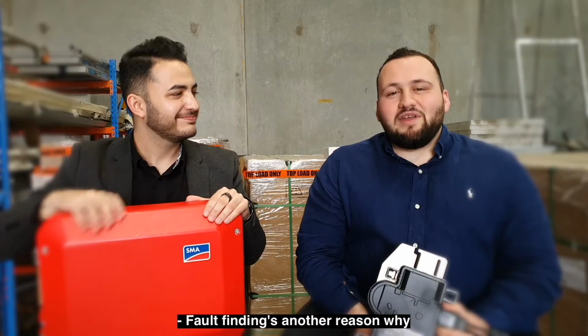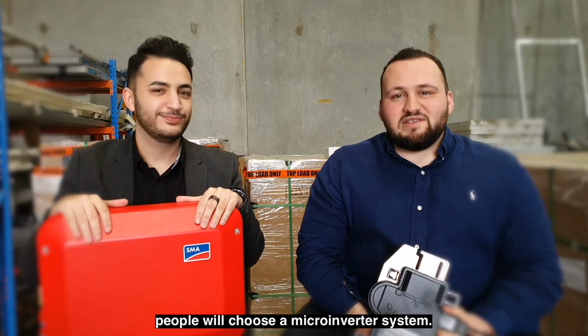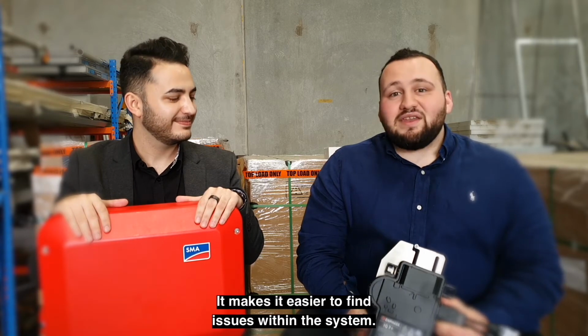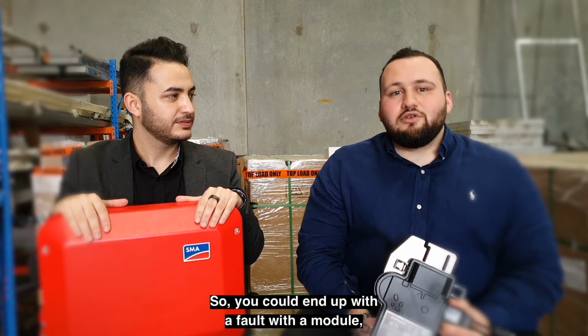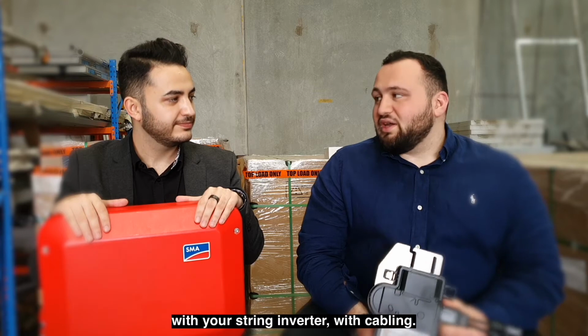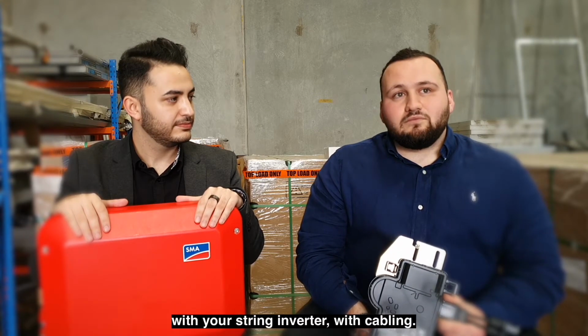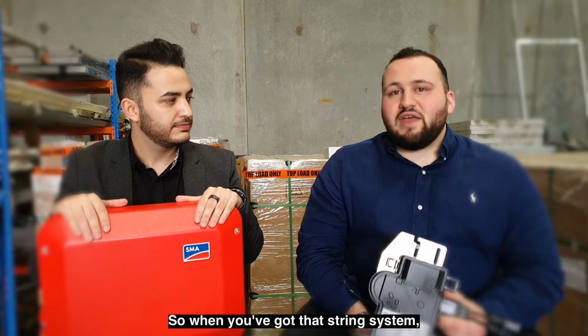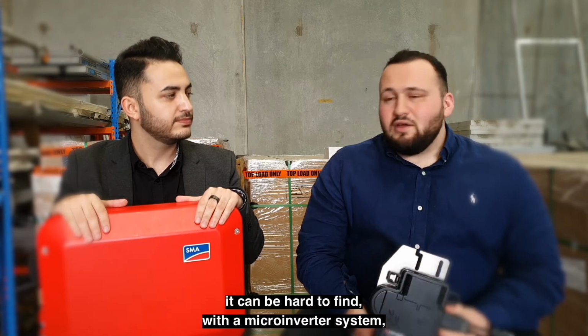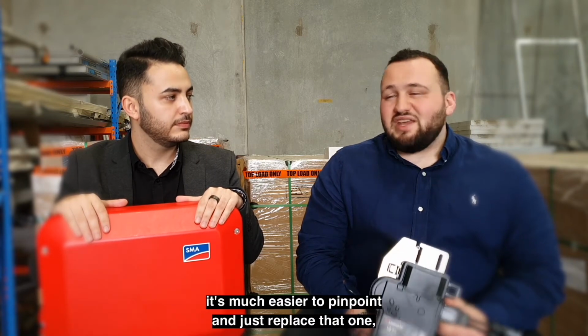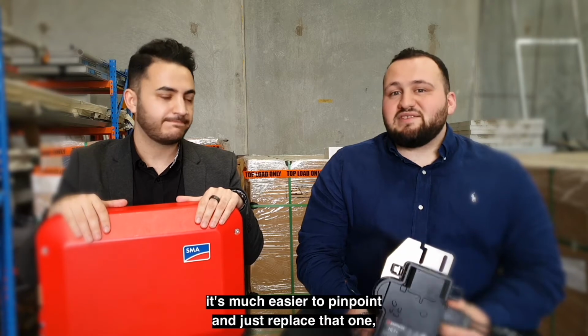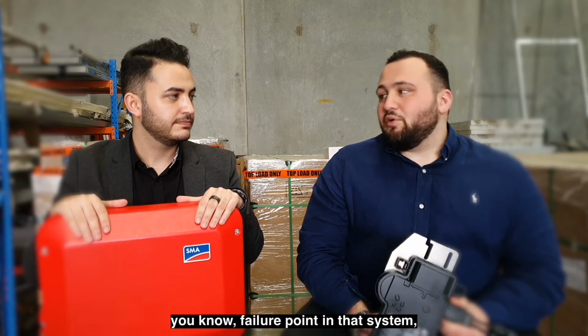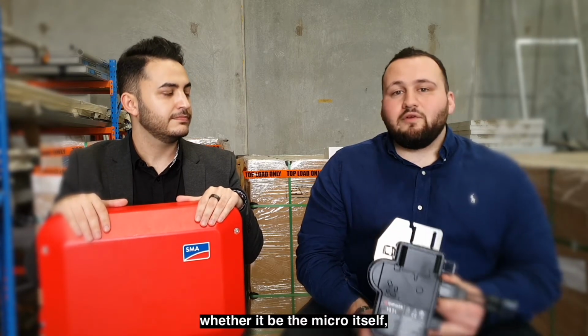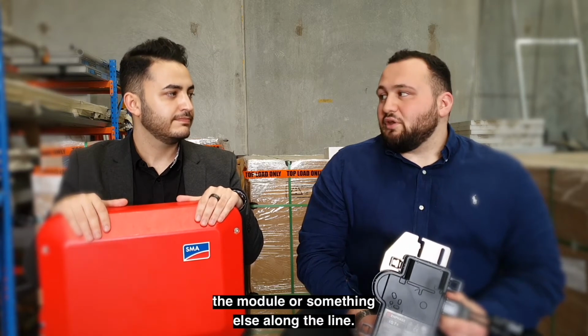Fault finding is another reason why people choose a microinverter system. It makes it easier to find issues within the system. You could end up with a fault with a module, with your string inverter, or with cabling. When you've got a string system, it can be hard to find. With a microinverter system, it's much easier to pinpoint and replace that one failure point, whether it be the micro itself, the module, or something else along the line.